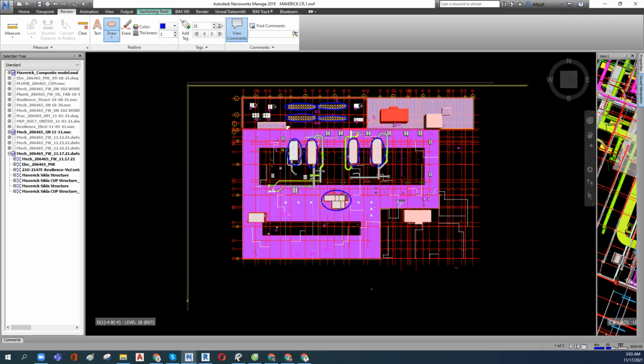So what typically happens is you exceed the allowable lineal footage per circuit, and that means you've got to add additional circuits, and there may or may not be those circuits available in the panels. The other part is the circuits that got left out for this are 120 volt, and you normally run 208 just to make sure you've got enough juice to push all that.